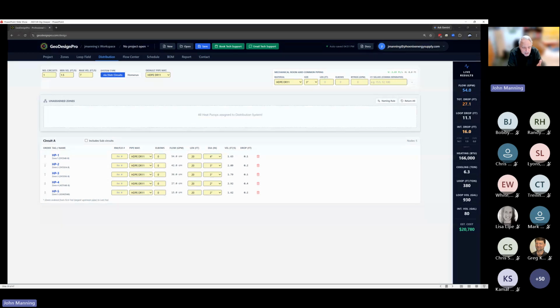The program tells you the flow rate, just for reference sake. You can specify the different length of the pipe upstream of the node or the T, that is the branch that's feeding a particular heat pump. The program calculates the proper diameter, which you can override if you want. So this functionality is all built in, and you can model the entire distribution system a variety of ways that I can't go into all of them today.